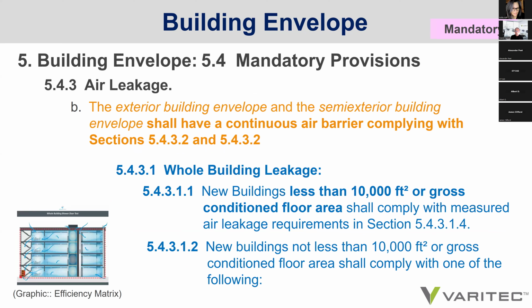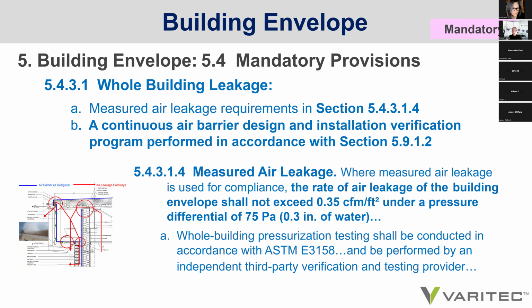Air leakage is significantly addressed in the language from the 2016 standard, and has been expanded upon considerably. And there is new language now on whole building leakage. New buildings less than 10,000 square feet of gross conditioned floor area shall comply with measured air leakage requirements. And new buildings not less than 10,000 square feet shall comply with one of the following.